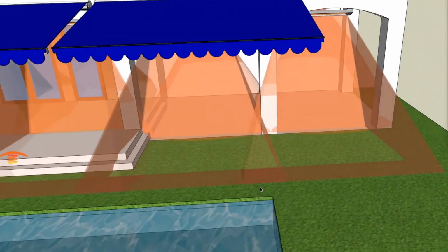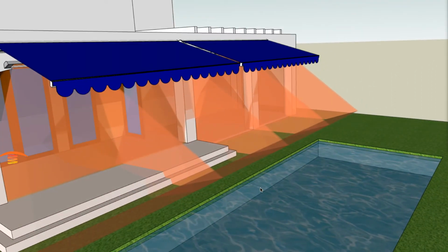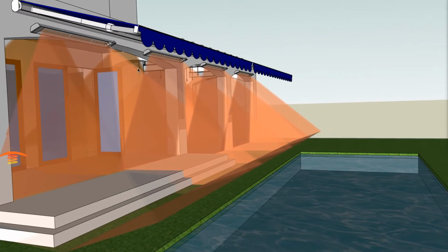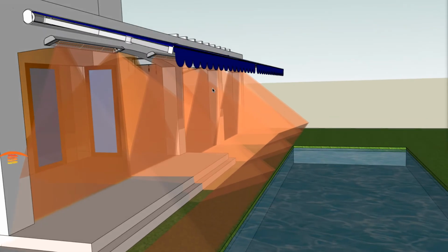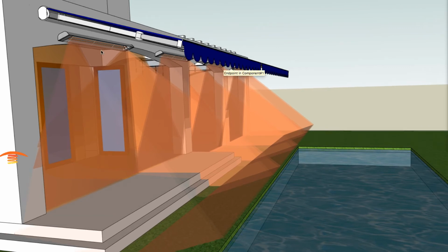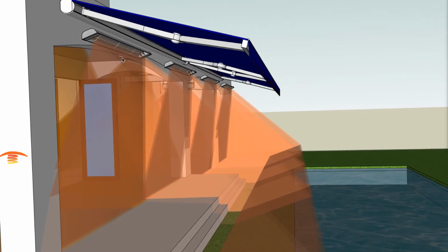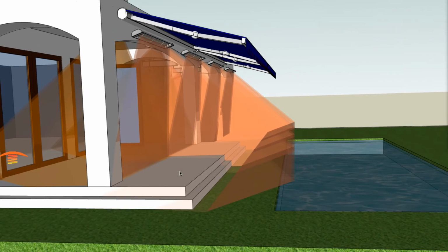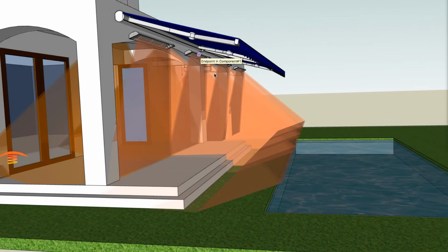But one thing to think about is residential applications. If you were running four of these 6,000 watt units, you'd need a lot of power, over 100 amps, just for that portion alone, and that might be an issue for the residents. So you may have to choose to have maybe two of these units only, or possibly just changing these out to a 4,000 watt unit, and you may not get the total coverage you're hoping for, or the intensity that you're hoping for down here, especially on cooler nights, but it'd definitely be okay up here. But with the 6,000 watt, you have that adjustability and the intensity that you're looking for.